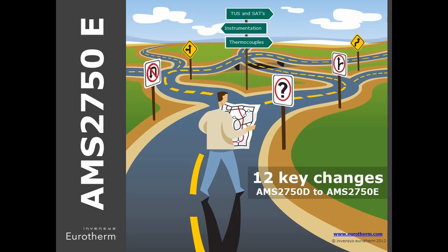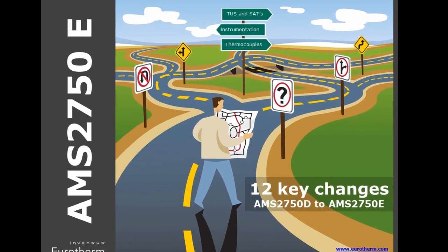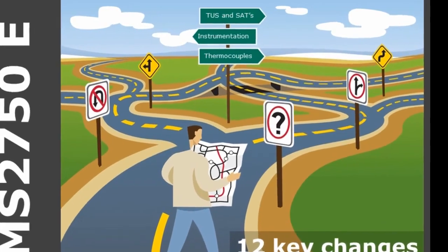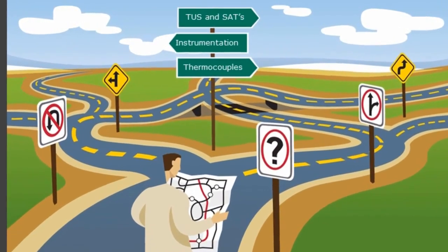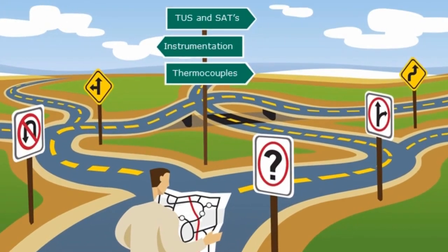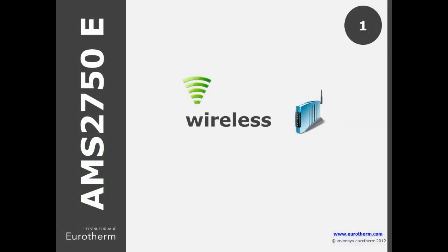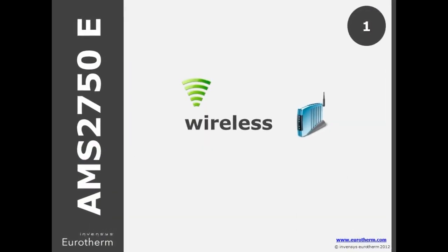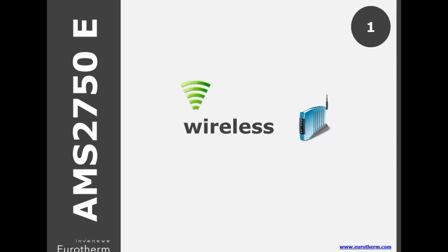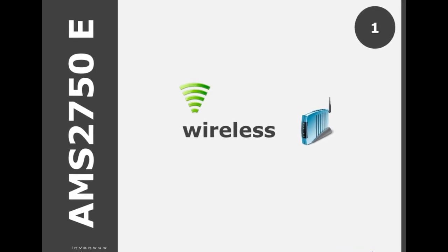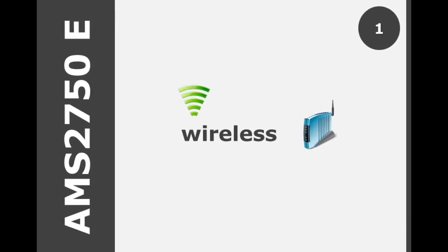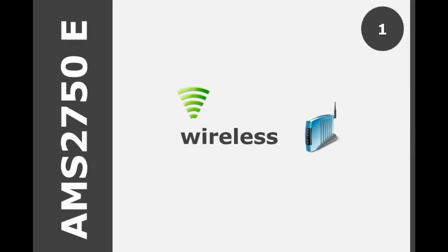This short video outlines 12 key changes between AMS2750D and the new E version released in July 2012. First point is that E now specifically outlines that wireless is allowed as an alternative to extension wire. This is not mentioned in D. It also notes this type of system needs to be part of the calibration check.